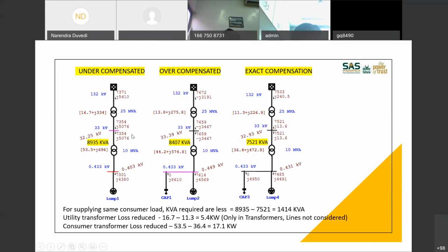In the second case, overcompensation, whatever reactive power you can see is actually overcompensated. In this case, the kVA supplied are 8407. And if you have exact compensation, where the power factor is close to unity, you can see that 7533 kilowatts are delivered with only 240 kVAR. So its power factor is almost unity. In this case, it goes down to 7521.